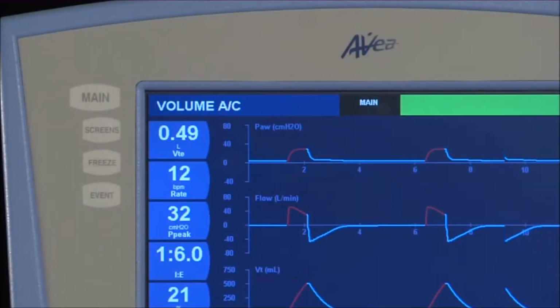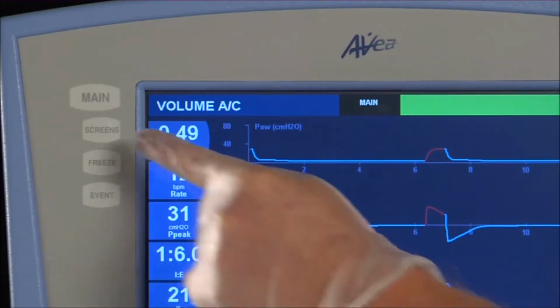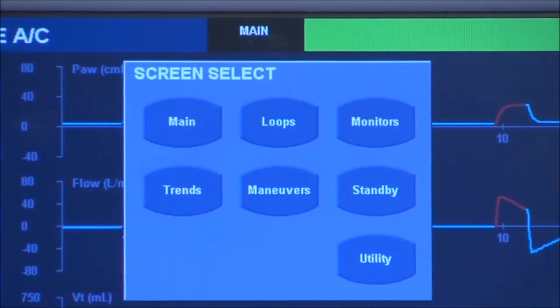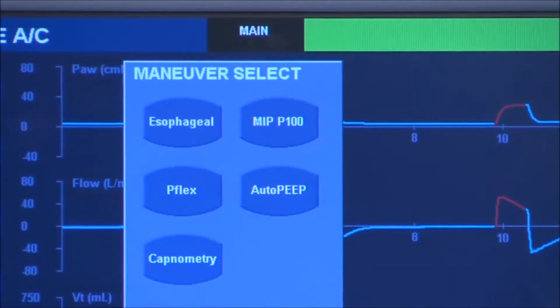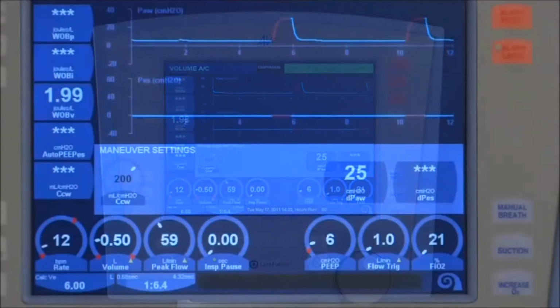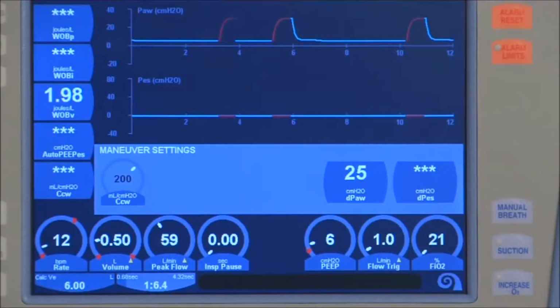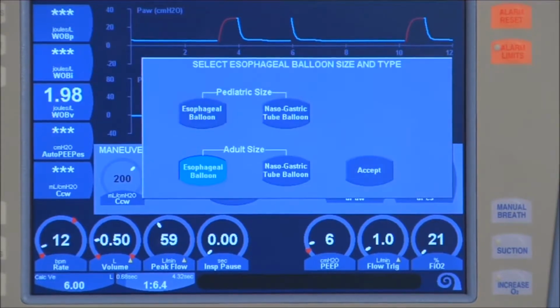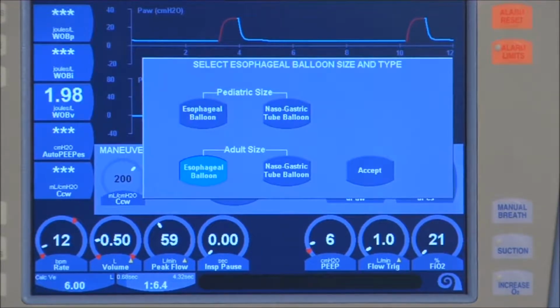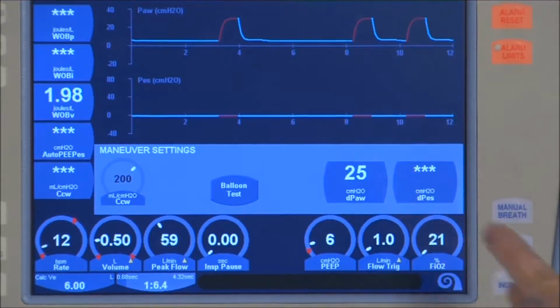When preparing the ventilator for transpulmonary pressure monitoring, you must access the esophageal maneuvers screen by selecting Screens, then Maneuvers, then Esophageal. You next select your balloon choice. Once your catheter is connected to the ventilator, the Maneuvers screen will ask the operator to select the appropriate catheter. Once accepted, an icon stating Balloon Test will be displayed.